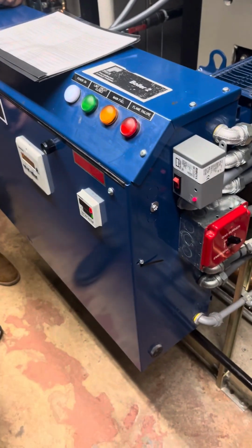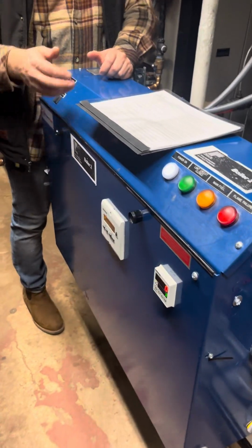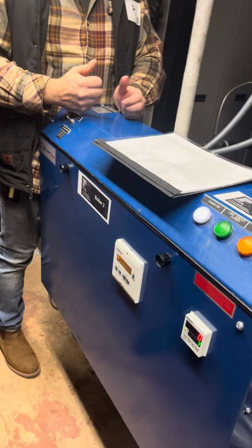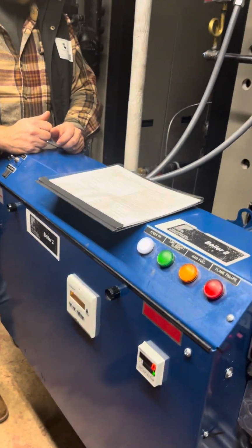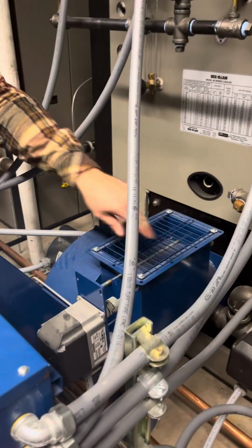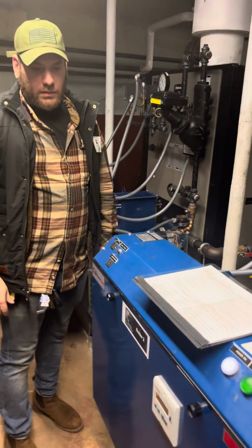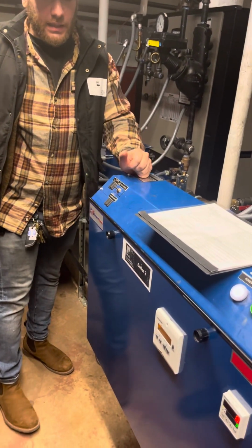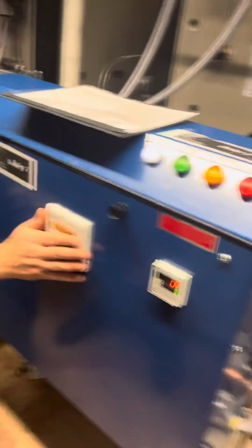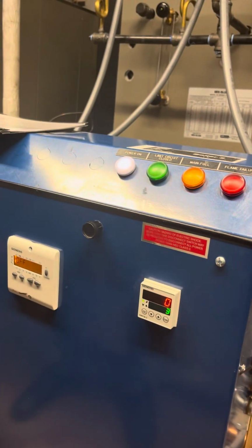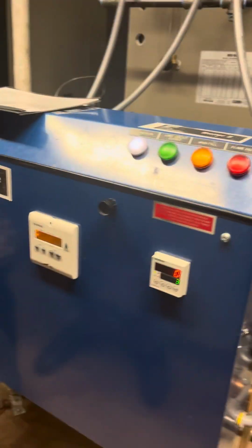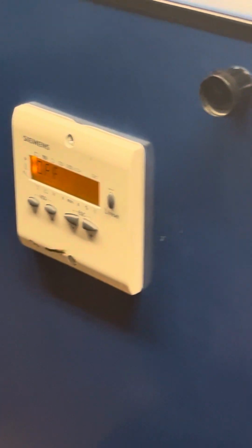The Siemens LMV, this is pretty much running the whole show. It's similar to your Fireye, doing the same operation. It's controlling these two servos, and it's controlling your fuel and air independently. It's the modern system called linkage-less parallel positioning. So if we come down here, I'll show you the ways to retrieve codes and then actually know what they're telling you.